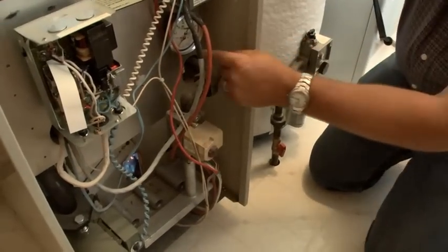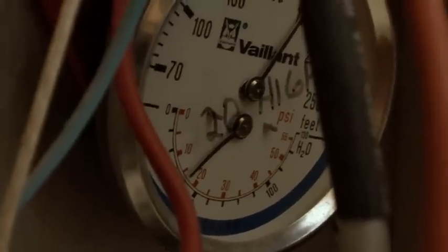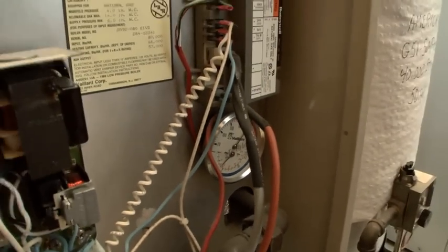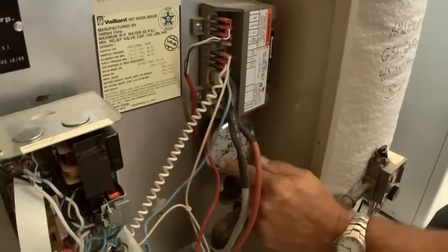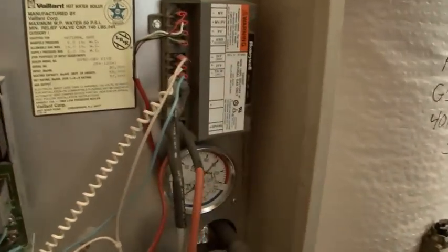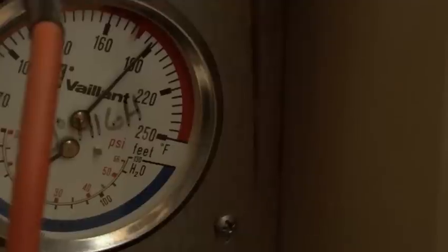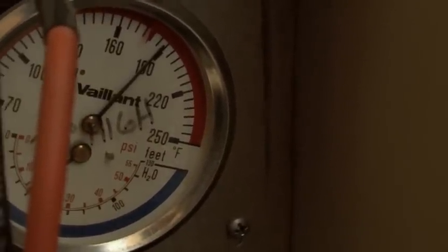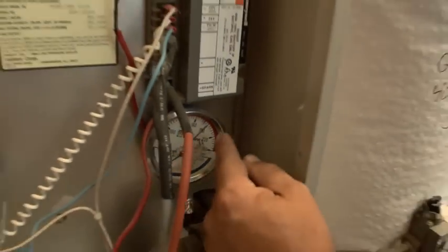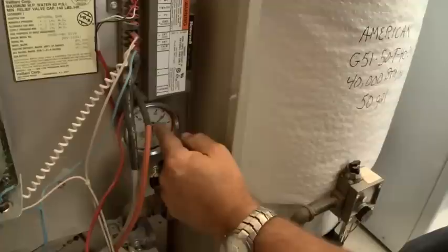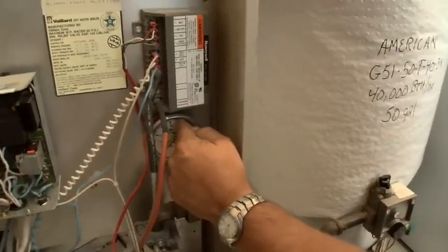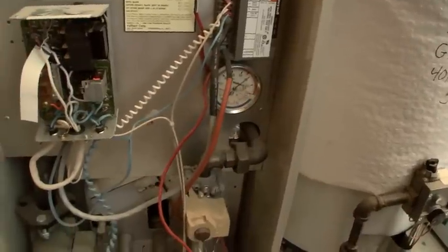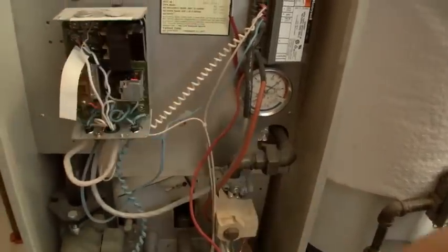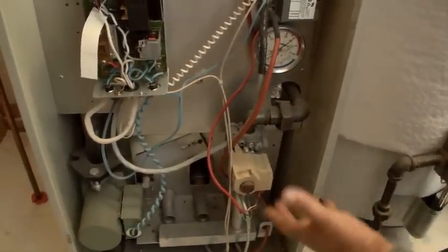The other thing we want to look at on here is the pressure, and right now we're running at about 16 psi, but we want to be in that 12 to 20 psi range on the pressure. If it goes higher, we just shut off a little under 190 degrees, our gas shut off. Now what will happen is we're going to deliver this heated water out to the baseboards. They're going to dump the heat. The temperature of the water is going to come back. It'll be cooler, and eventually this will drop back down, probably around 160, 150, somewhere in that area, and then the flames will come back on. During this whole process, as long as there's a call for heat, the pump continues to run, and we just cycle on and off the gas.